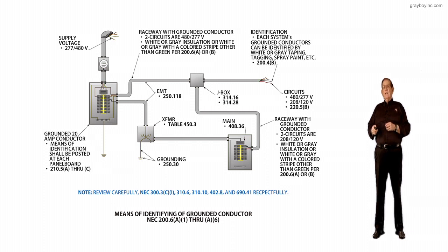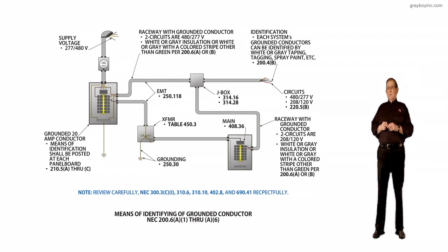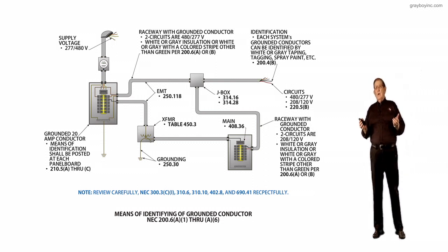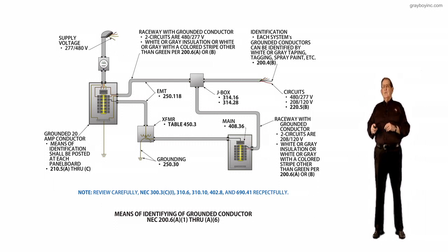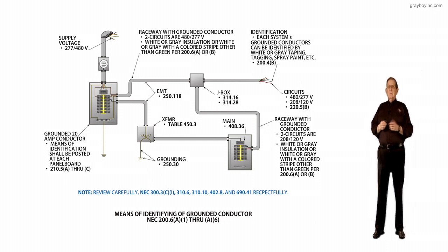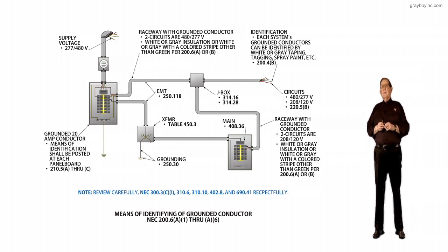Now you notice the grounded conductor coming in here, if you had, say, from the transformer to the panel board there with 480, with, say, 208-120, because it's a 480 volt primary. Then 408.36 would list your main here, and the main would protect the bus and so forth. But notice this main is allowed now in a panel board. You have to have a main. You couldn't put just 6 individual mains anymore in that panel board, because that is the main circuit breaker to disconnect those circuit breakers below it.